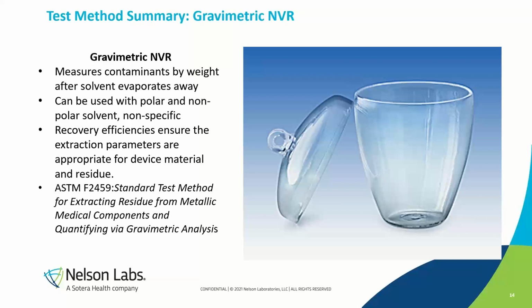So after the 30-minute sonication, we let that solvent evaporate all the way off. So we're left with the solid residue that we've pulled from the device. And that's what we take the mass of and report. So it's just a non-specific lump of residue, a microgram per device. It's a more sensitive test method than you would expect due to how we've improved techniques over time and how we've been able to control the background noise. We have pretty good sensitivity for an NVR test. It's pretty comparable to TOC, not as sensitive as THC, definitely not as sensitive as a GCMS.